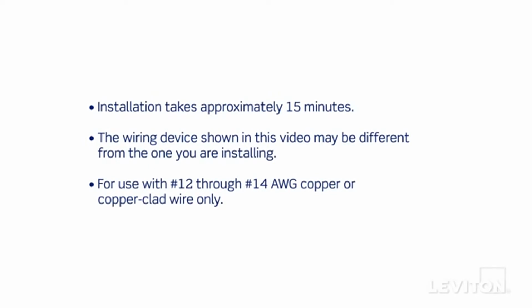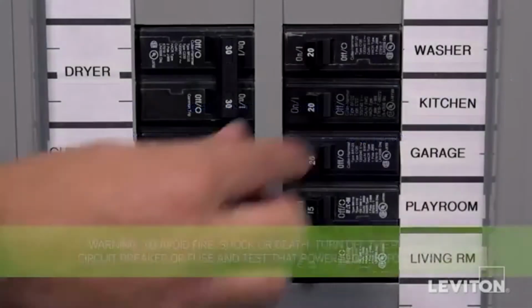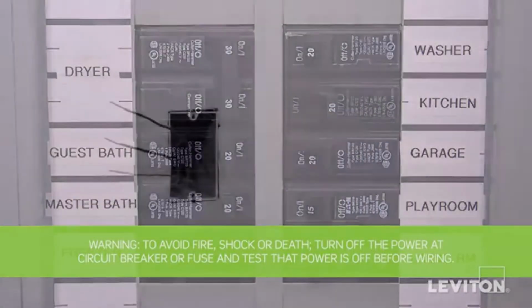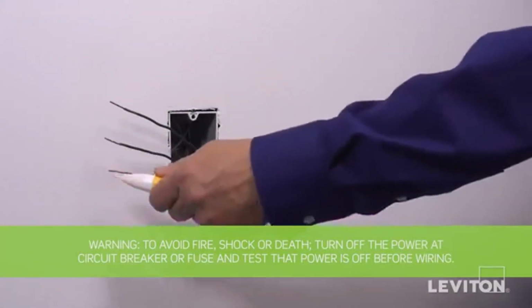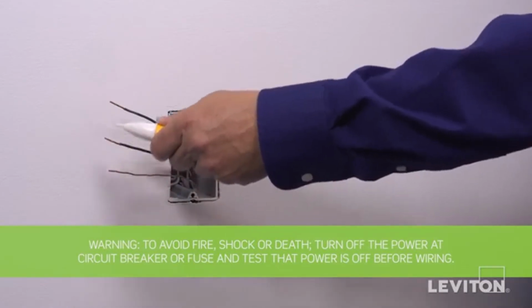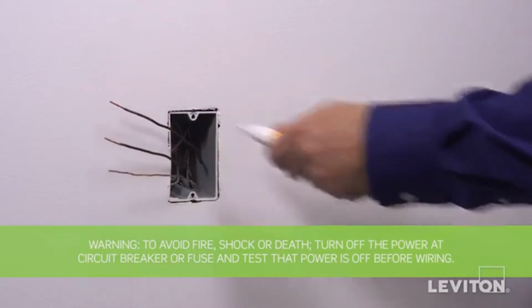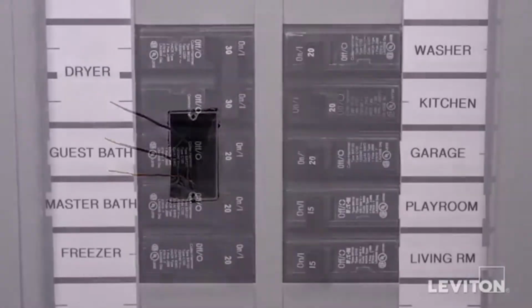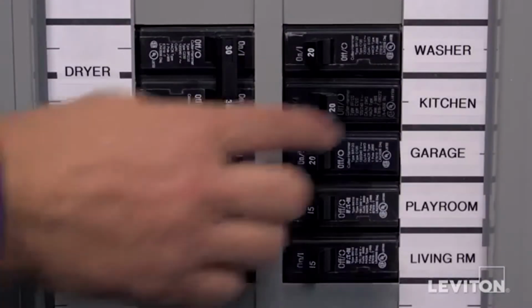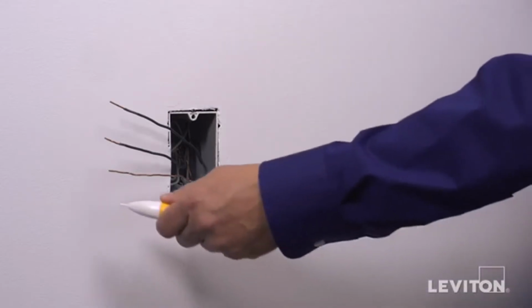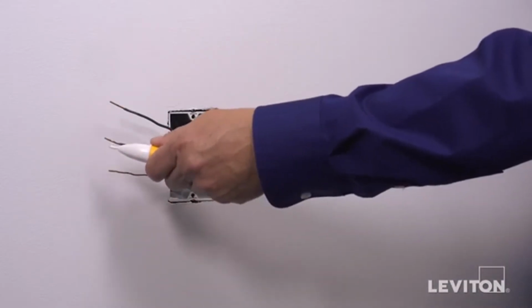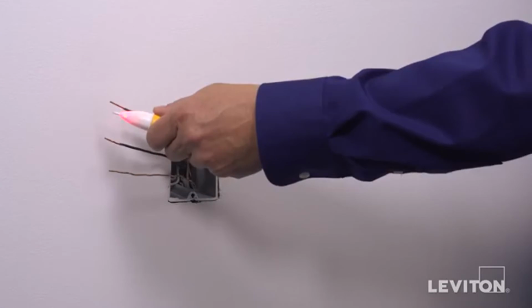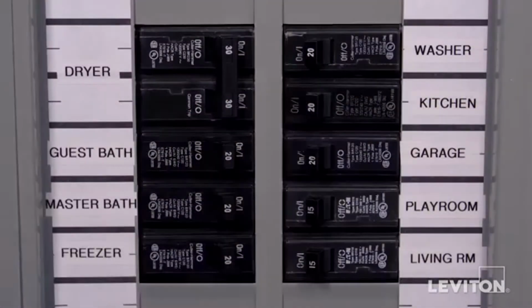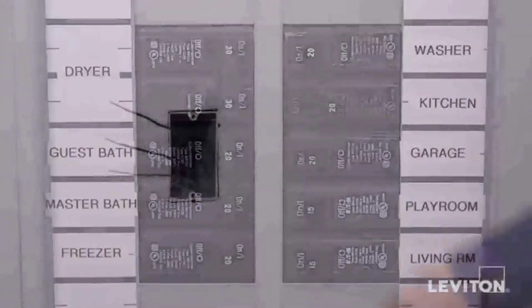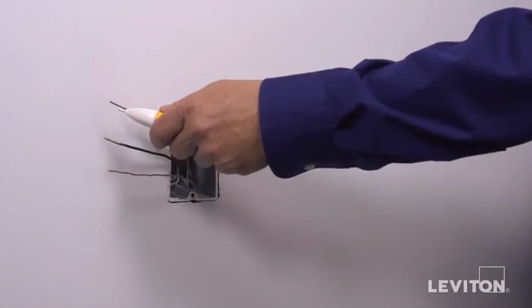Local codes take precedence. Be sure to turn the power off at the circuit breaker and use a voltage tester to ensure that the power is completely off. Now, we need to identify the hot wire. To do this, turn the circuit breaker back on. Carefully use the voltage tester to test each wire. The hot wire will be indicated by the tester. Once identified, turn off the circuit breaker to shut power and test to ensure the power is off.